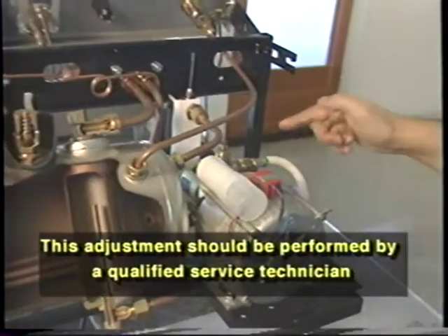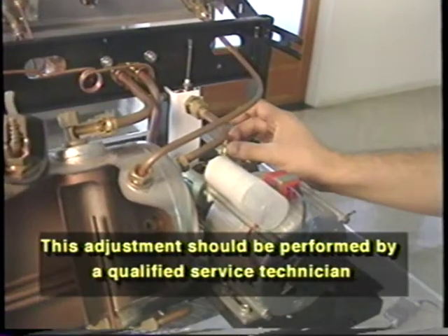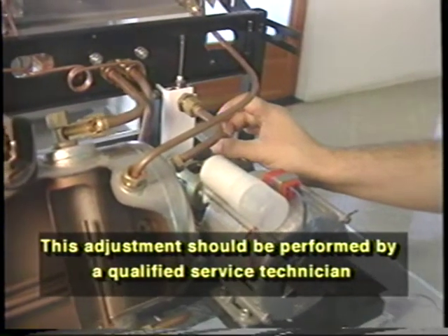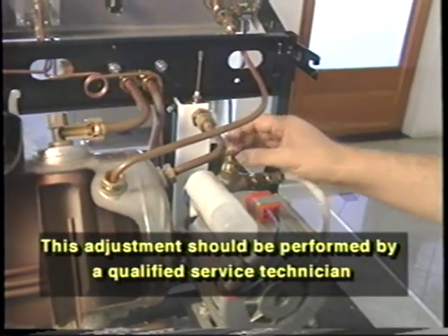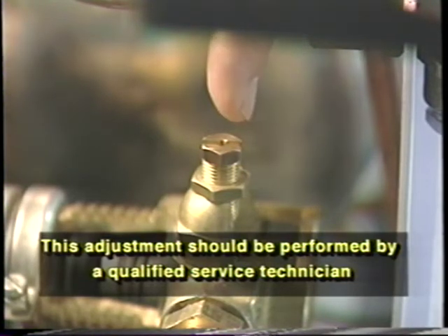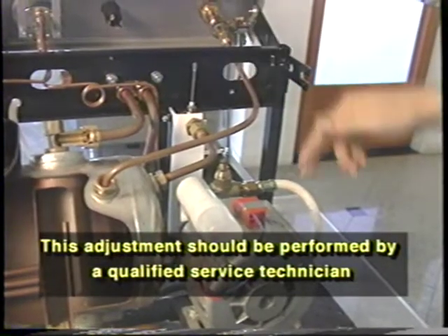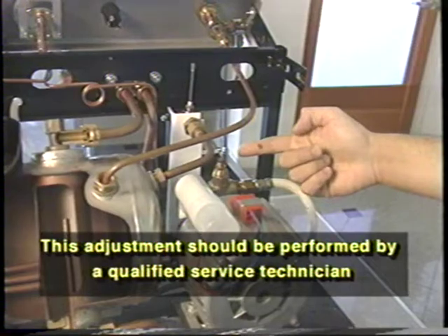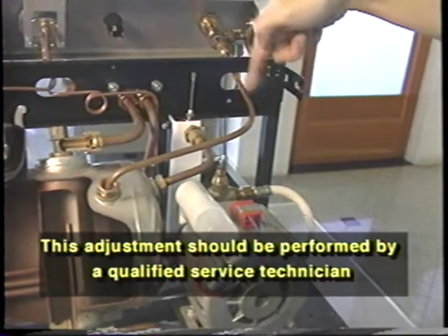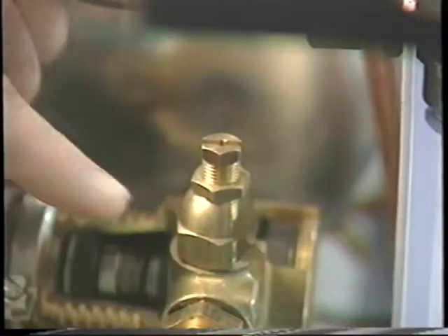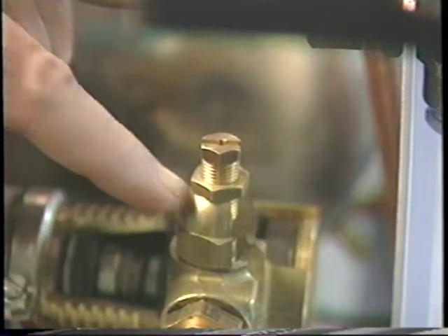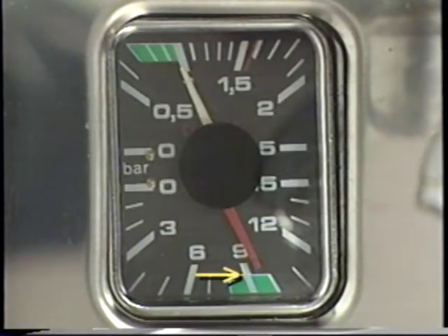If you want to adjust the pressure on the pump, essentially on the pump you will have one of these lock nuts right here that gets backed off, and by adjusting the adjustment screw by turning it clockwise, you increase the pump pressure. Counterclockwise, you reduce the pressure. But once you lock it in, you turn this nut right here and you're locked in. You should be at 9 bars.